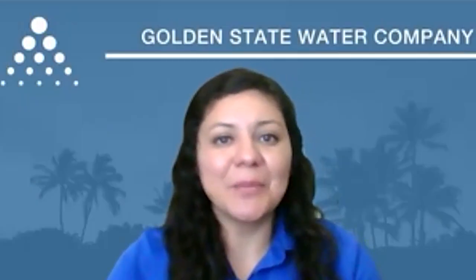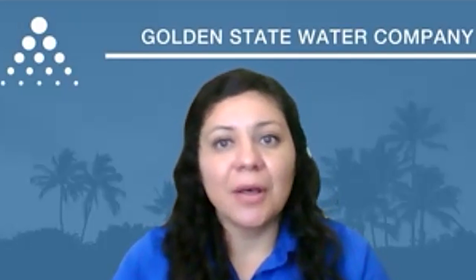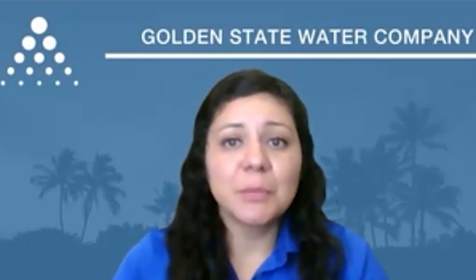Certainly, Nadia. Golden State Water System's sole source of water on the central coast of California is groundwater, no surface water. As such, providing customers safe drinking water introduces unique challenges. We must utilize the groundwater sources available to us and treat to meet compliance with all state and federal standards. The groundwater sources for our Edna system have selenium concentrations that exceed the MCL. To address this, we have installed ion exchange treatment to bring selenium to acceptable levels, therefore ensuring safe drinking water.